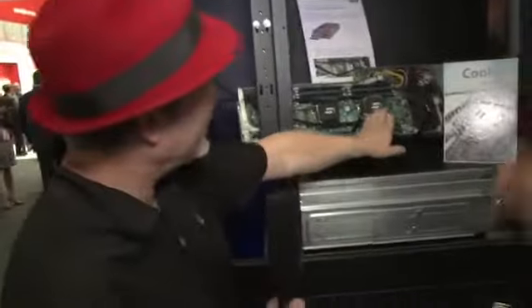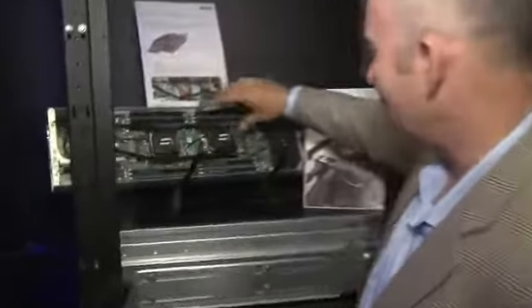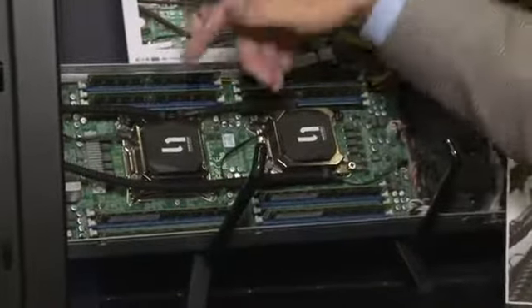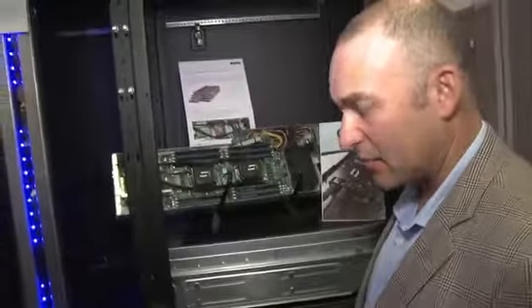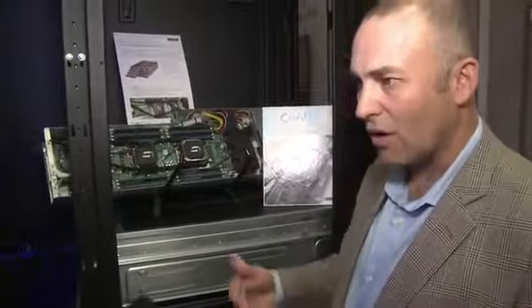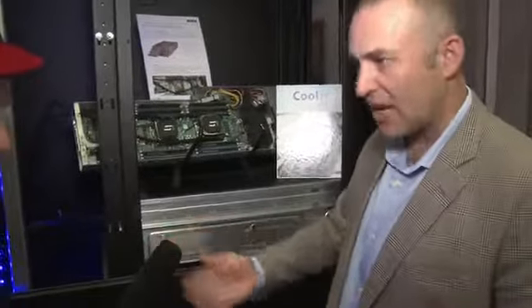In terms of integrating these solutions, we've developed a very low-profile cold plate module — it's only 15 millimeters tall. That gives us an ability to integrate liquid cooling into even the most dense form factors, whether it be blades or more innovative open compute designs. We haven't yet found something we can't fit our liquid cooling modules into with relative ease. We removed the pump from the server module, keeping the same form factor externally, and now utilize our patented split flow technology which provides very low pressure drop and very high performance cold plate capability, with retention options for Intel, AMD, NVIDIA sockets and more.